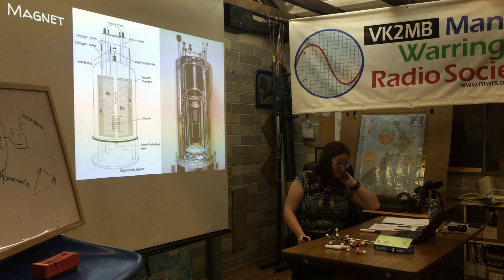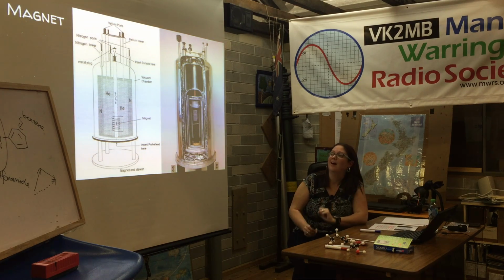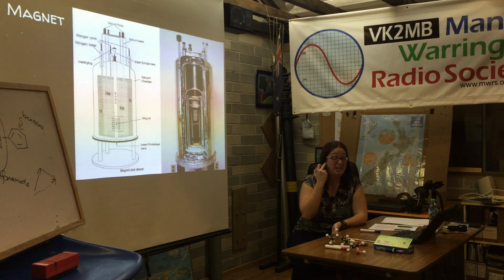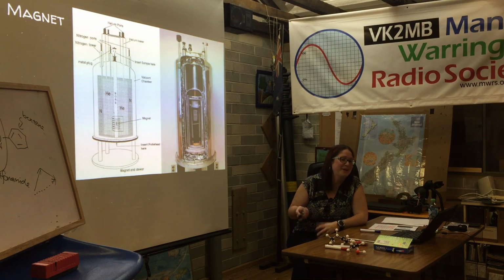So the magnet, as the first point. In the GE video that I showed you first up, they talked about superconductivity and how you've got a solenoid which is kept super cool in order to remove the electrical resistance. So in practice, there isn't absolutely zero resistance. You do lose current over time, but it's not enough to be concerned about. For example, they checked one of the machines at UNSW a couple of years ago and it had 300,000 years left. So I'm not even worried about that. It's as near to forever as makes no difference to mortals.